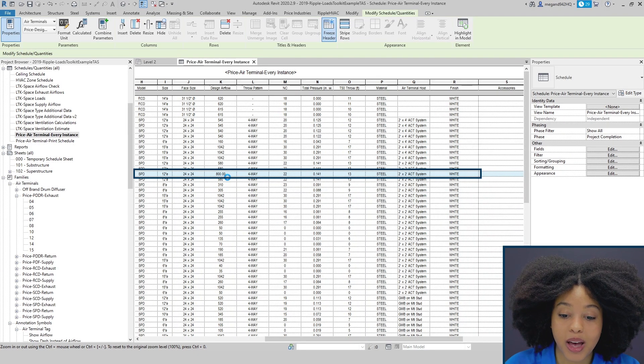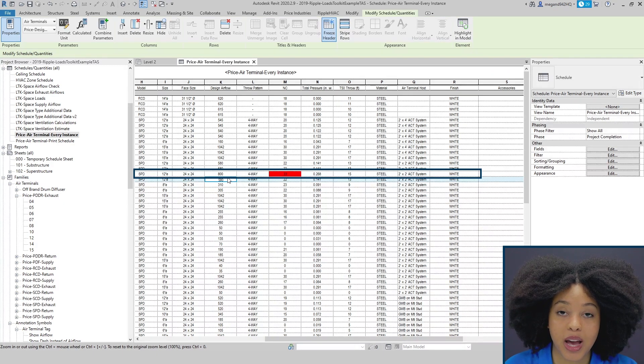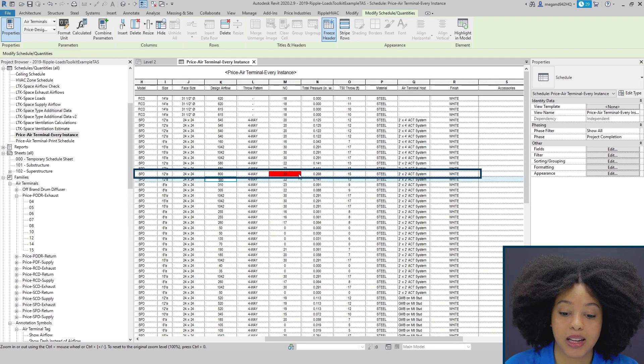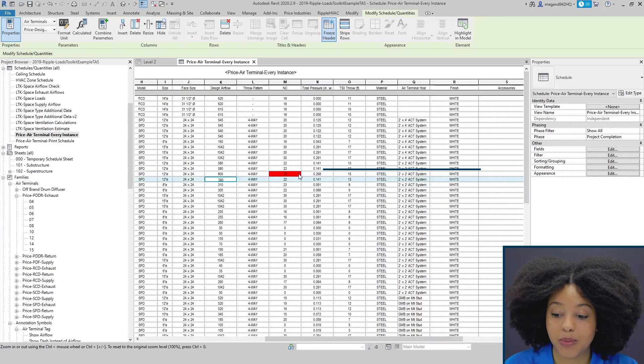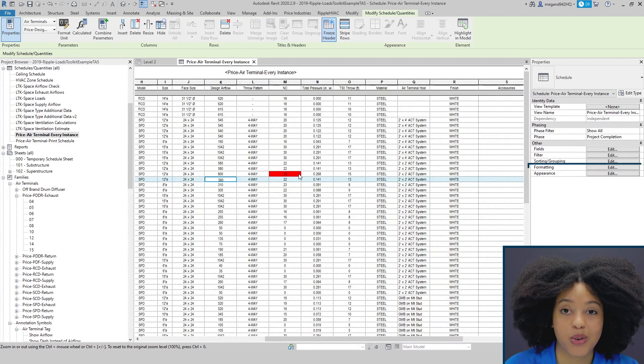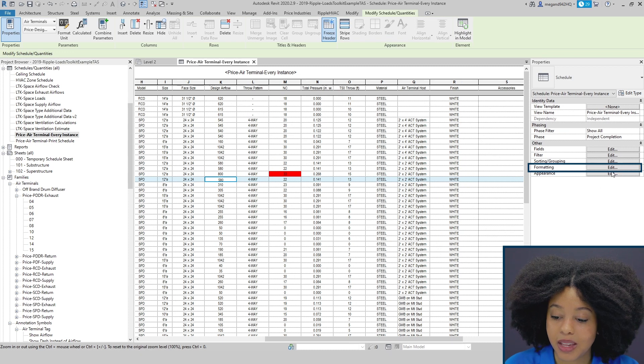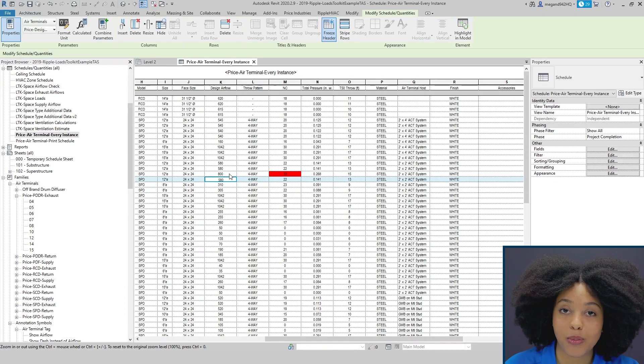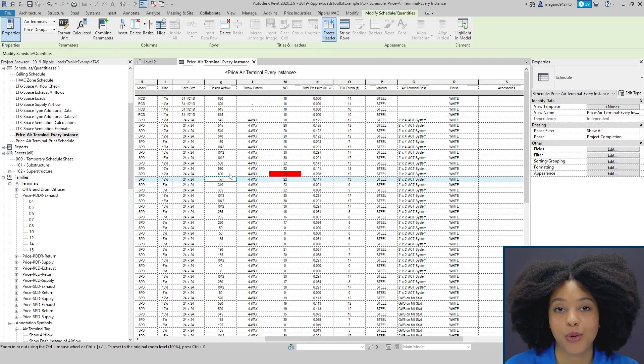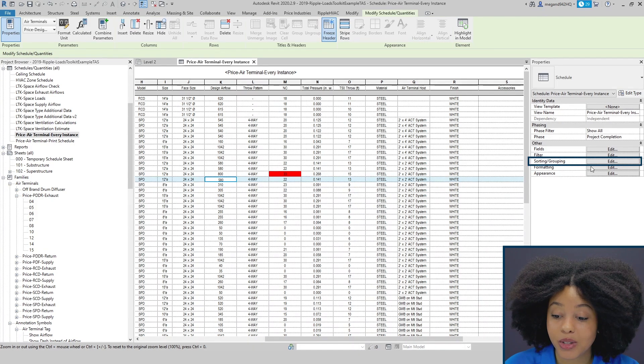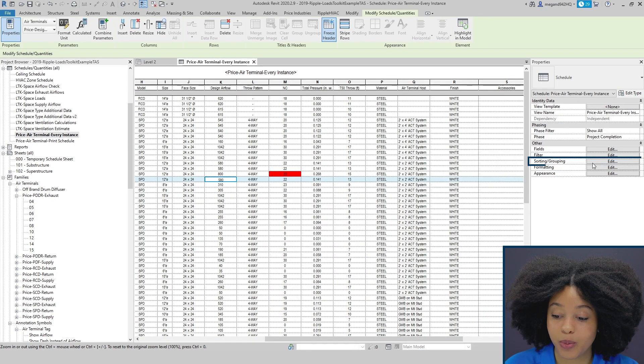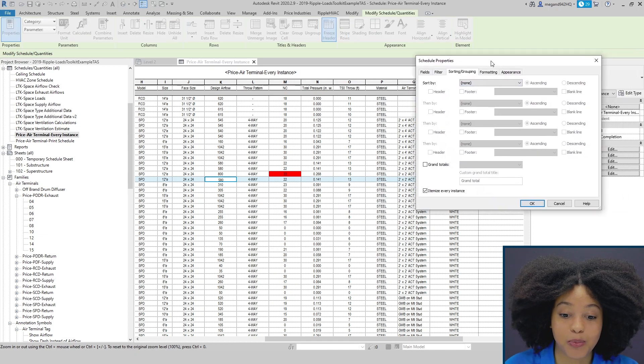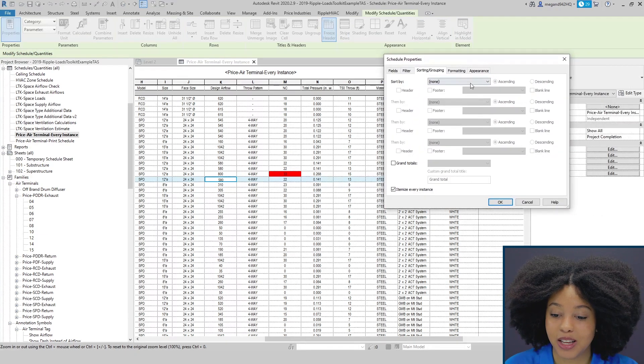You also have the ability to change the limits for your NC. Here we currently have it set to anything above 30 NC will give this red warning. This can be manually adjusted by just going to conditional formatting. It's also important to note that by changing the design airflow it won't automatically replace the diffusers in your space and it won't automatically resize your inlet.